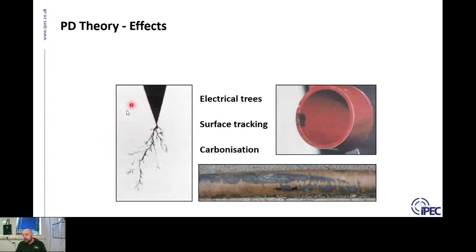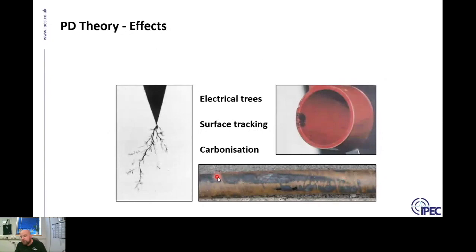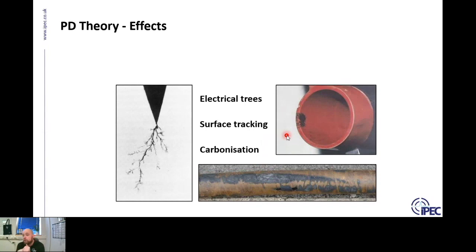A typical electrical tree in solid insulation is shown — if you have a defect, over time this electrical tree forms and eventually leads to failure. The bottom image shows an oil cable where PD occurring in the paper cable insulation caused a carbonization effect. Stripping back a few layers of a cable in Chatham, Kent, we can see where PD was occurring before the cable was repaired. On terminations, PD can occur from contaminated insulation, and you might find surface tracking and carbonization evidence on the outside of termination components.